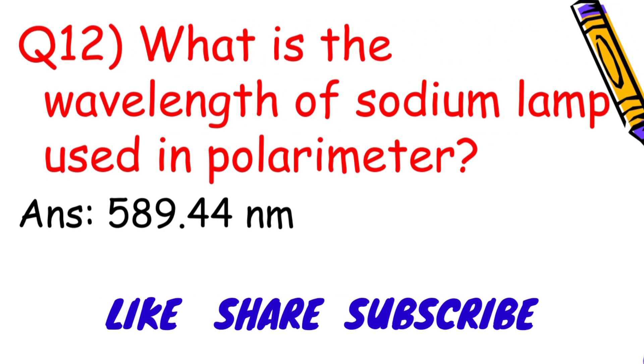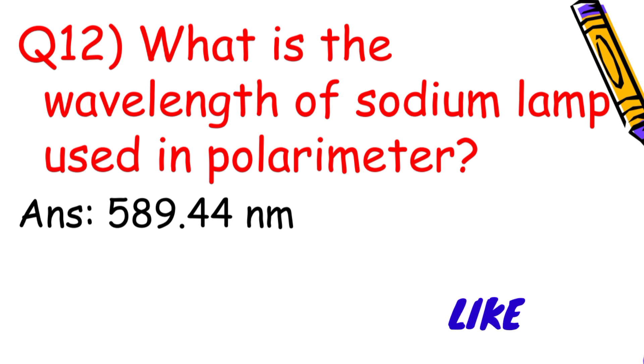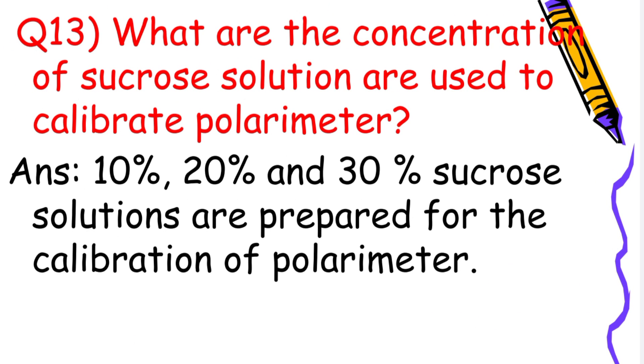What is the wavelength of the sodium lamp used in a polarimeter? The answer is 589.44 nm. What concentrations of sucrose solution are used to calibrate a polarimeter? 10%, 20%, and 30% sucrose solutions are prepared for the calibration of a polarimeter.